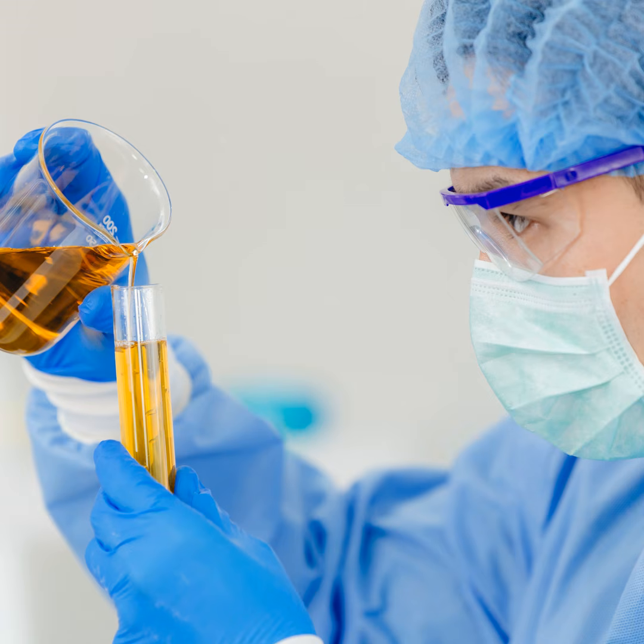There's another interesting characteristic of this scale. Imagine you're flushing contamination out of a hydraulic system. Initially, you may remove a very large number of particles, yet the cleanliness code barely changes. Then, as the system becomes progressively cleaner, relatively small improvements can cause the cleanliness code to change much more quickly. That's simply the way the classification system works. It's not that filtration suddenly becomes more effective, it's just the mathematics behind the cleanliness scale.